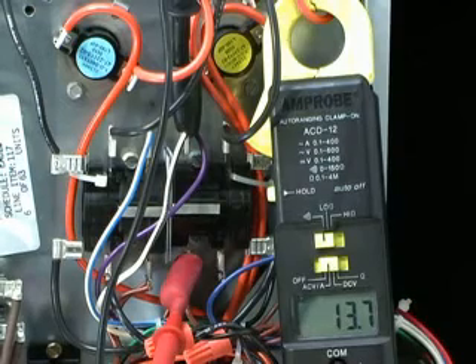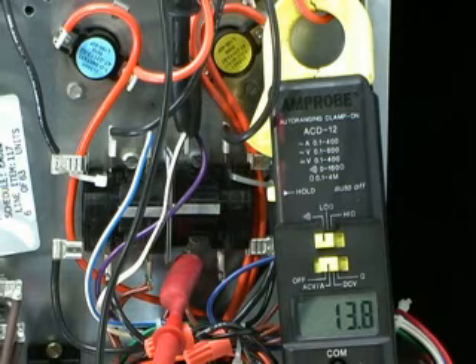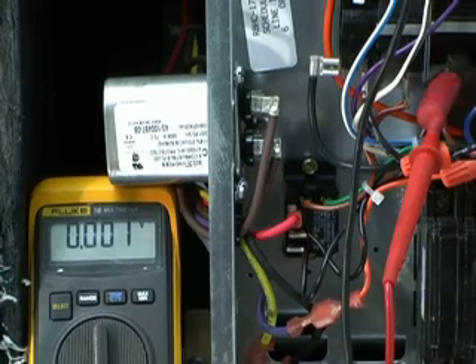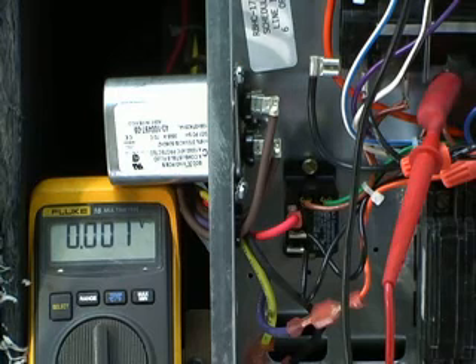Now once I found the wire that was carrying current, I just traced it down to the sequencer, and I found it was the one on the right side. As I say, it's possible the sequencer is just stuck, but before you make that assumption, you've got to check, make sure it's not getting voltage. So I've got the meter probes now hooked to the two 24 volt terminals on it, so we'll see if there's any voltage telling it to come on. And as we see, it's not, so we know it's a mechanical problem with that sequencer.